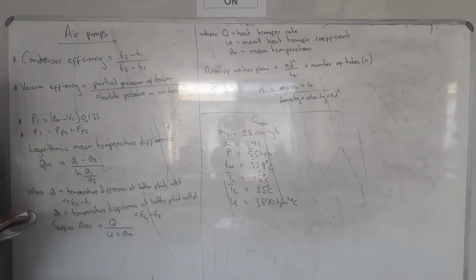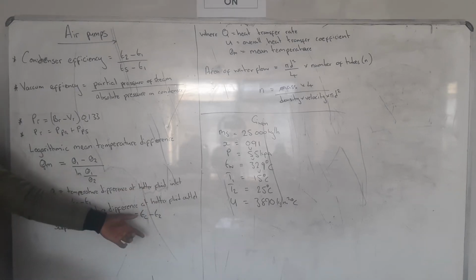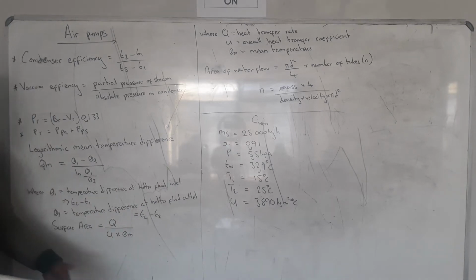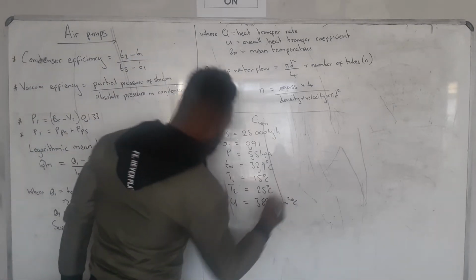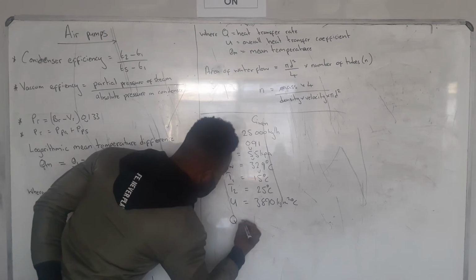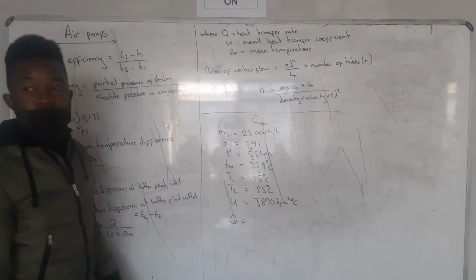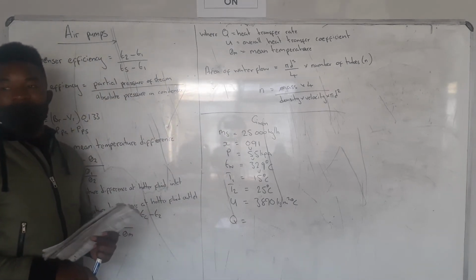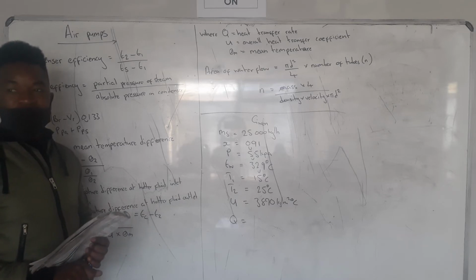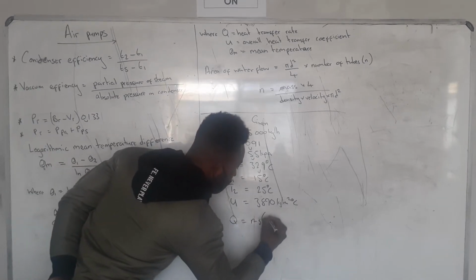They said a surface condenser dealing with 25,000 kgs of steam. So we are talking about the steam. So if I'm calculating my heat, it must be the heat of the steam. Alright, okay. So what is the formula to calculate the heat of the steam, guys? If you can still remember. I said it's MS H2 minus H1.